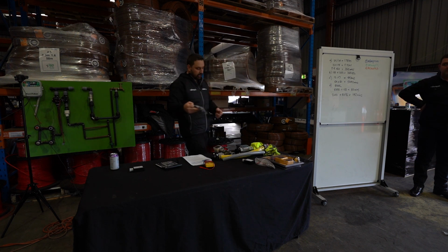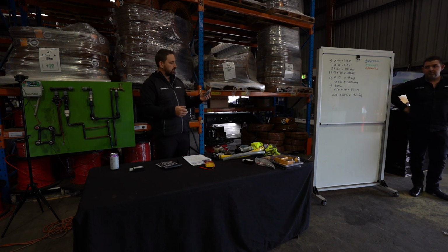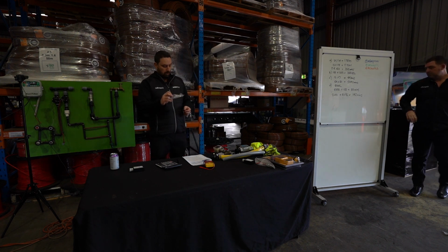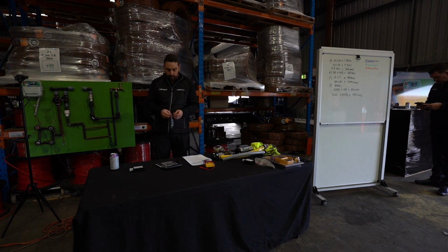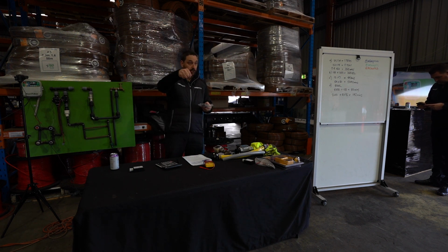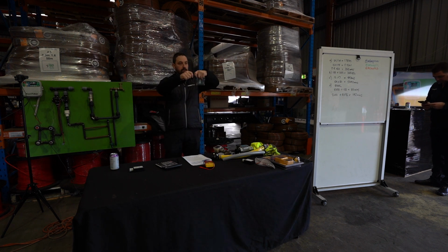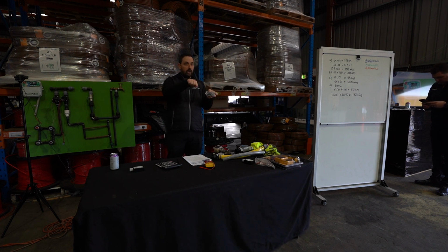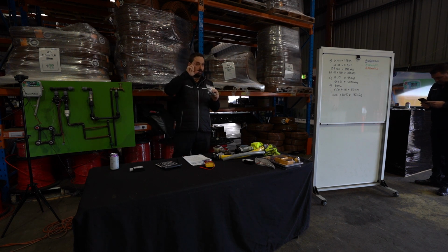Pretty similar to that, but again from an audible standpoint, is what we call a valve locator or a chatter unit. The chatter boxes have been going around for quite a while. What this unit does is you've got alligator clips on it. Pretty straightforward. You basically wire in at the controller point, because you know where your controller is. You take it out of the wires of the controller, and between the controller and the wire you put this unit in between the main line, and as there's power going down the line, this thing's basically chattering that electrical current on and off at a fast pace.